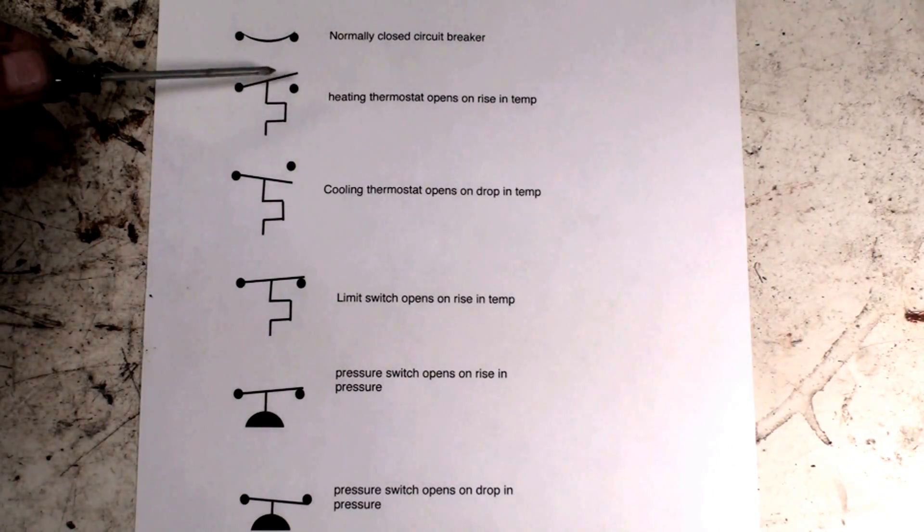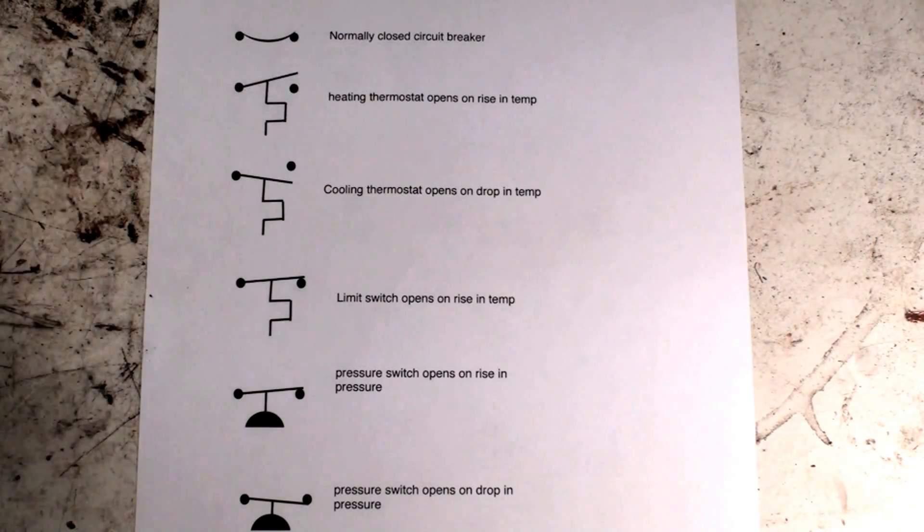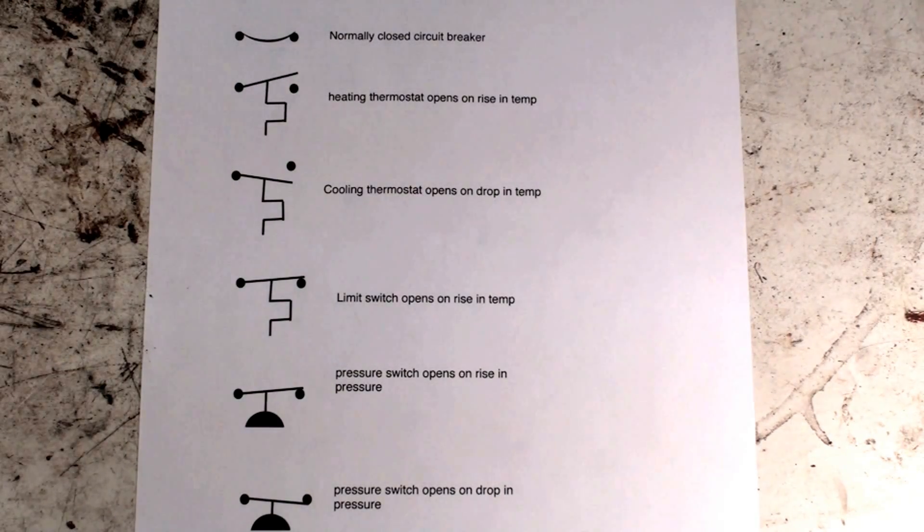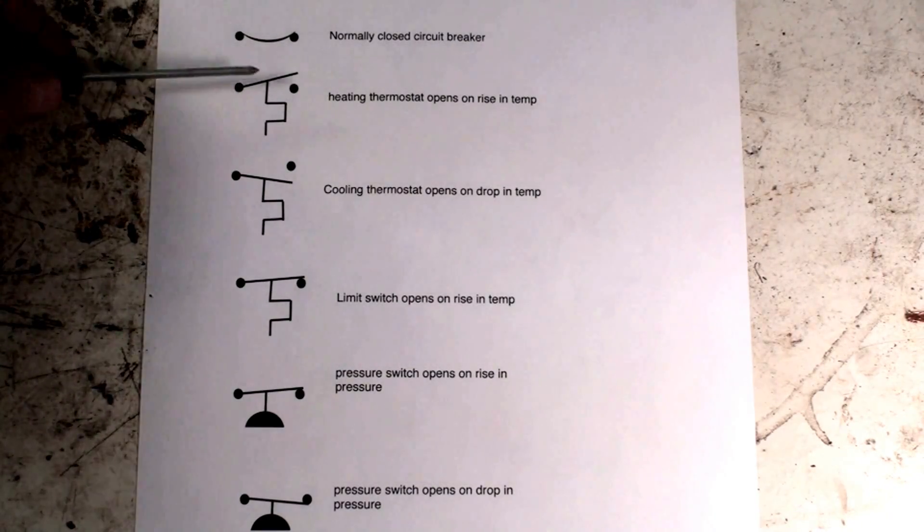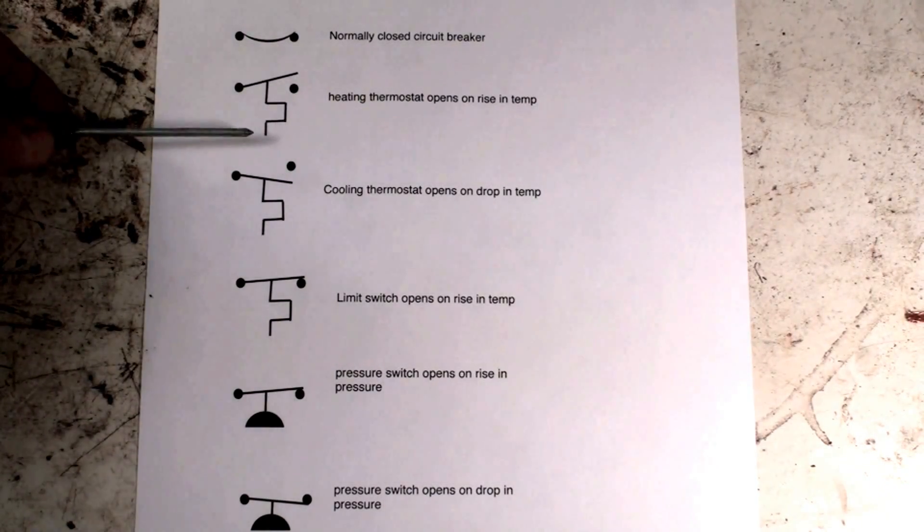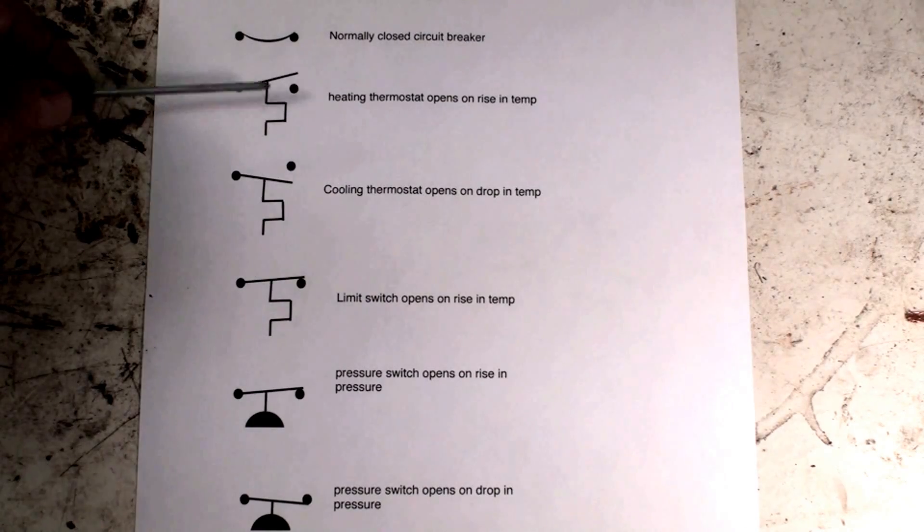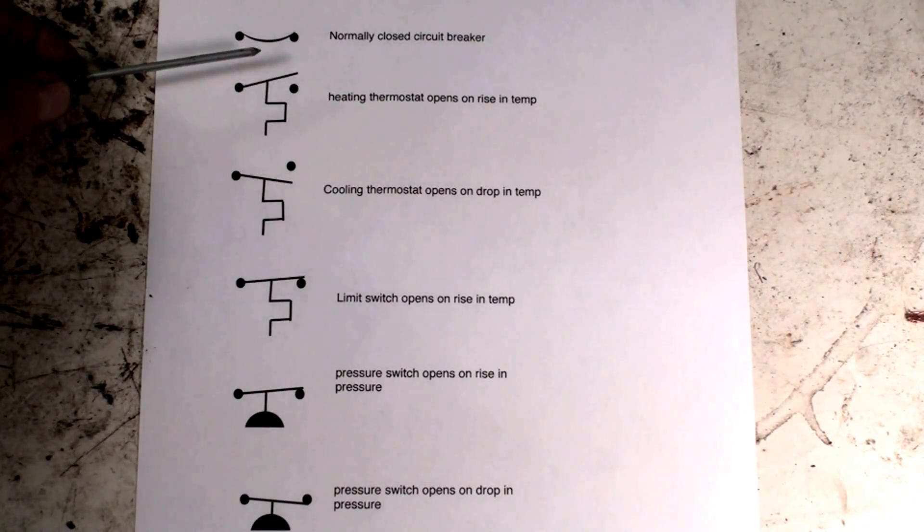Now this is an operating thermostat because it's shown in the open position. As I go through these things, I'm telling you how most diagrams are set up. I would not guarantee every diagram is going to be the same - it would be nice if it was the same, but they're not. You're just going to have to tough out some of these things because they have different designations sometimes. But these are just general ones that are usually fairly close. Anyway, if it's got this little squiggle on it, it is operated by temperature. It's a heating thermostat - it opens on a rise in temperature.